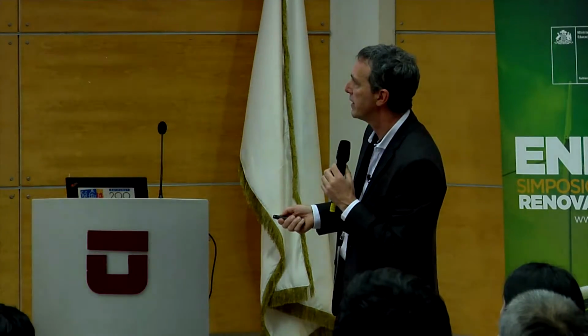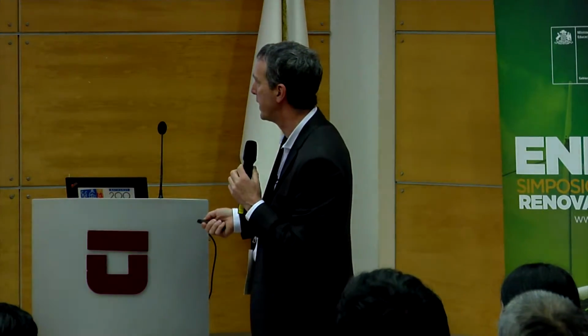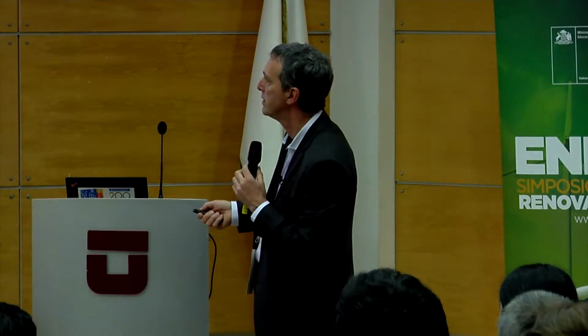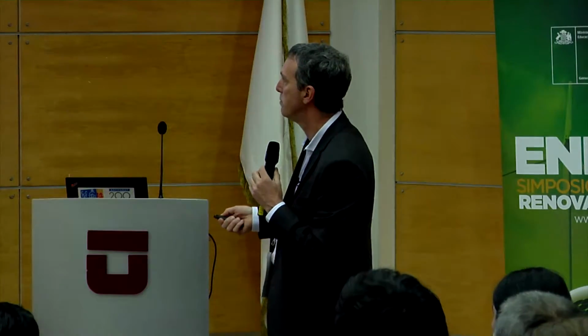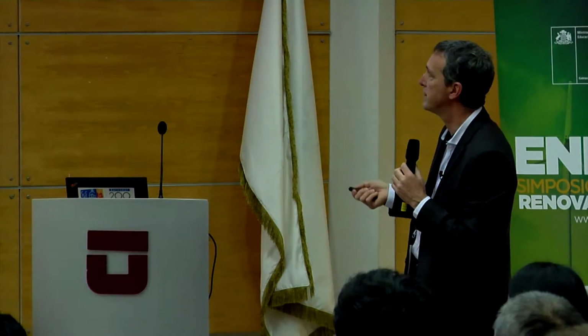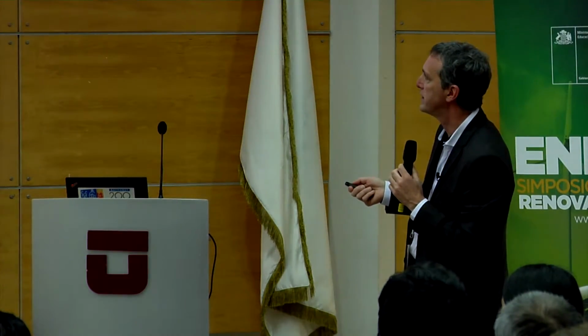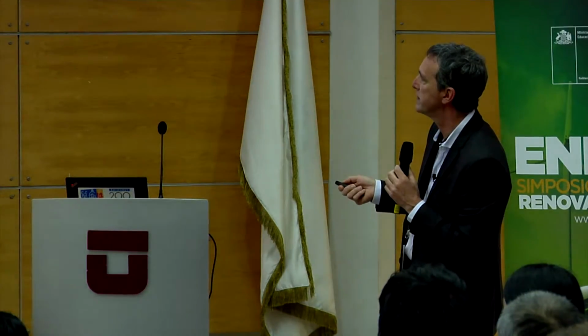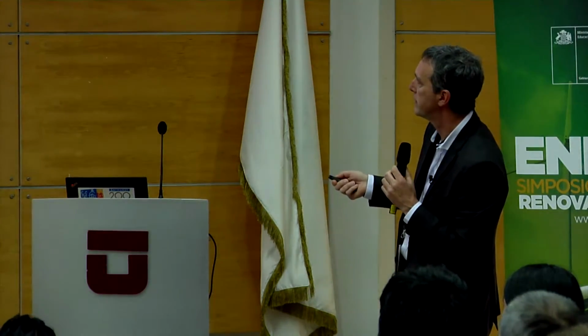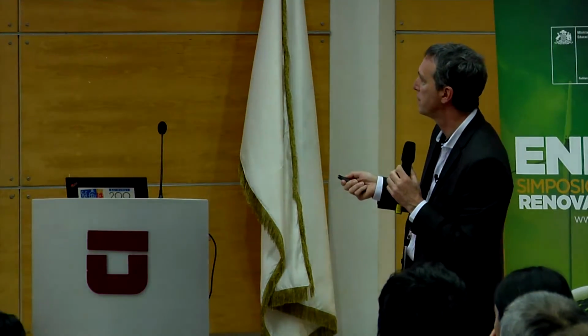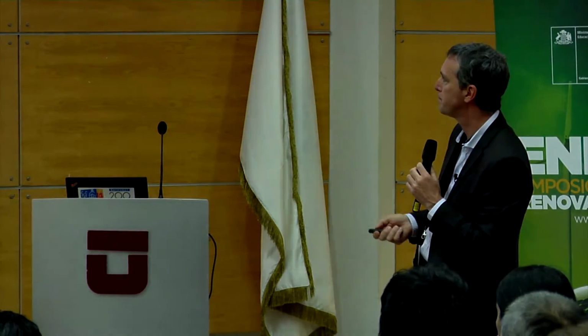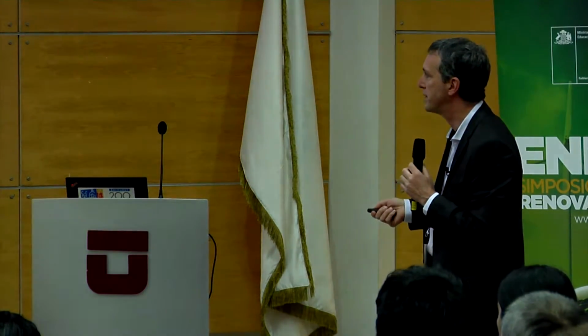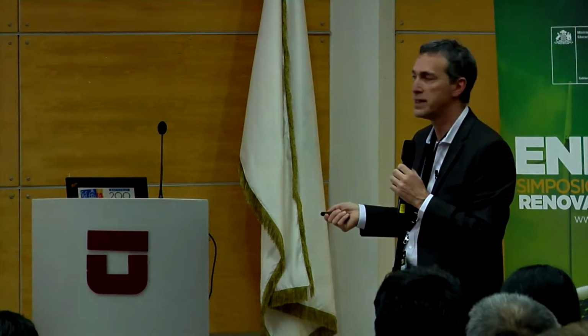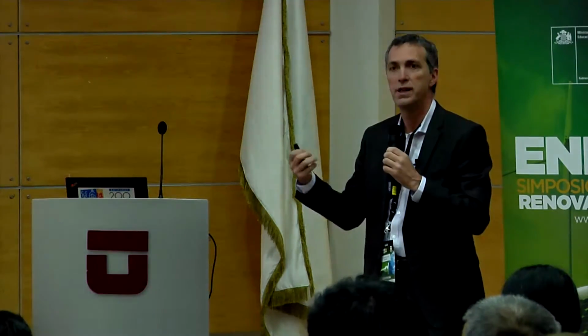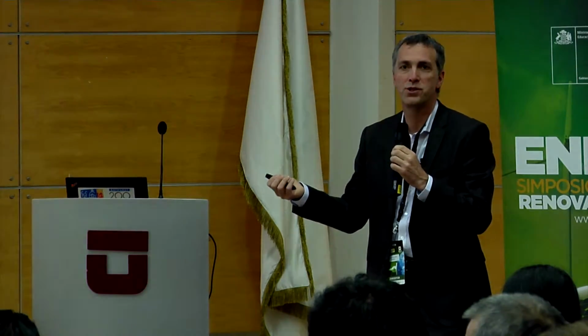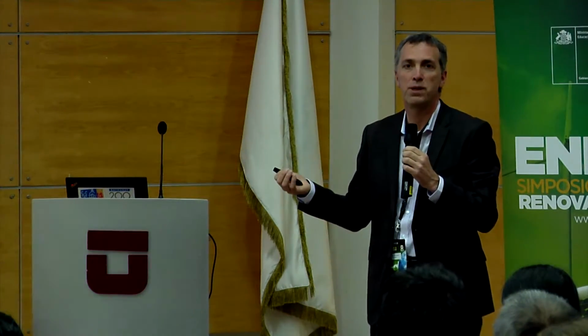So the red is the supply current. The green, as you can see, is the 7-level multi-level voltage, and the supply voltage is the blue figure. On this side, we can see the power flow from port 2 to port 1. As you can see, the current at port 2 is in phase shifts of 90 degrees compared to the voltage, while on port 1 they are in phase. So now, as I said, the switching frequency of each of the devices in the converter was 250 Hertz in order to maintain a low switching frequency, since this converter needs to be used for very high power.